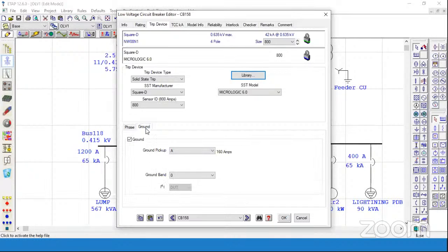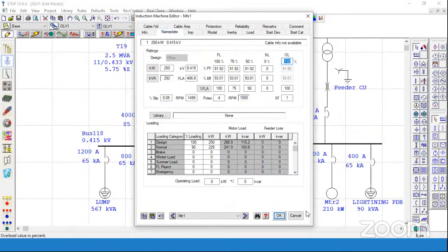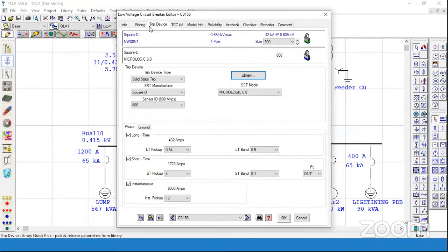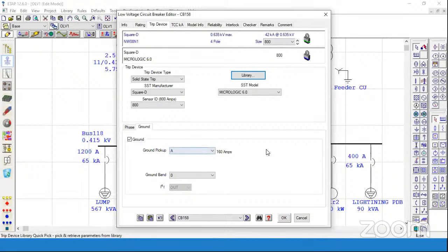Now for ground fault protection, normally the setting is done for 20% of the full load. But here for this Micrologic relay, the parameter ranges are from A to J, and for every parameter there is a certain current range. You can see that if I change the setting value, the range also changes. So we take 0.2 times the full load current, that is 406 ampere. 0.2 into 406 is about 81 ampere, but the minimum available range is 160 ampere. So we will go with 160 ampere here, with a time delay of 0.1 seconds.